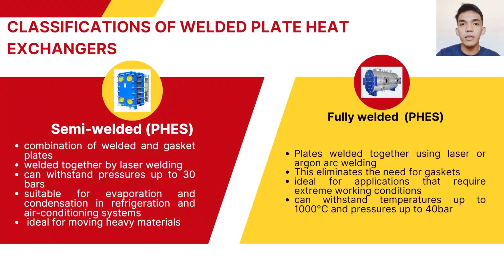Next is the fully welded plate heat exchangers. So, these are advanced type of plate heat exchanger that are constructed from a series of corrugated metal plates welded together using laser or argon arc welding. This eliminates the need for gaskets, allowing the fully welded plate heat exchangers to withstand higher temperatures and higher pressures than the traditional gasketed plate heat exchangers. So, the fully welded plate heat exchangers are ideal for applications that require extreme working conditions such as high temperature and high pressure, and are commonly used in thermal processes such as the superheating in heat recovery systems, refrigeration interchangers, and heaters of organic chemicals such as solvents, vegetable oils, steam, and batch reactors.